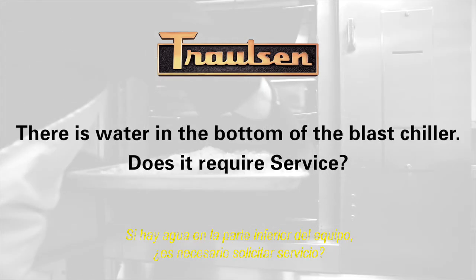There is water in the bottom of the blast chiller. Does it require service? Water in the bottom of the blast chiller is almost always caused by 1. The door not being properly closed, forming condensation inside the cabinet. 2. A long chill cycle by time. Or 3. Setting a freeze cycle with uncovered product. In the latter 2 scenarios, moisture removed from the product freezes on contact with the very cold cabinet interior and then melts away afterwards, leaving water on the cabinet floor.